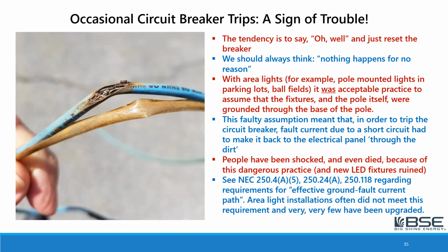For example, this is a little piece of wire that we had to take out of a lighting pole for area lights. And you can see that the insulation was damaged and the copper strands inside the insulation that were then broken or cut had been arcing periodically against the inside of the metal pole. But because it didn't contact the pole continuously, every now and then there would be a tripped breaker. But there's a tendency when that happens for the operating personnel to sometimes say, oh well, and they just reset the breaker. And then because this is an intermittent fault, usually nothing happens for a few months until the next time that it trips again.